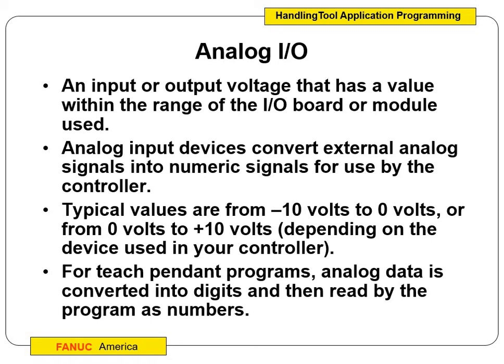Analog signals are an input or output voltage that has a value — the range of the I/O board module. That's how we use analog signals: they convert external analog signals into numeric signals for use. It's kind of like using the signal voltage to do our controls. The values can vary from negative 10 to zero, or zero to 10. So 8.75 might mean something, or 6.25. Remember, analog is more precise — it's not necessarily an on or an off. For teach pendant programs, analog data is converted into digits and then read to the program as numbers.